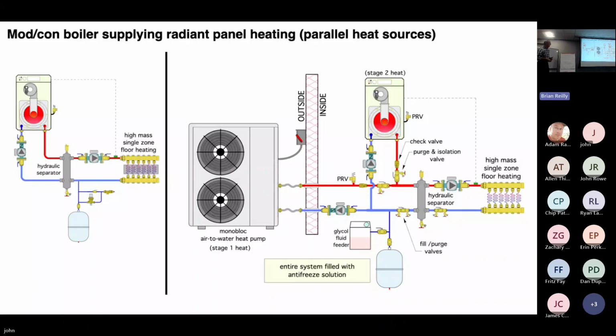If you're going to do a system like this into, let's say, a fire station, where you have a slab and you have large overhead doors, oftentimes the thermal break is non-existent, where the slab goes out under the door out into a ramp. Ideally, there'd be a nice piece of insulation there, but that's a hard detail, especially in a commercial garage, because that's a high stress area, the slab. So oftentimes you'll find that the slab just inside those overhead doors gets cold if you stop the flow. And if the flow's off for several hours and it's extremely cold out and it's just water in the system, what do you think can happen to the tube that's right next to that door?